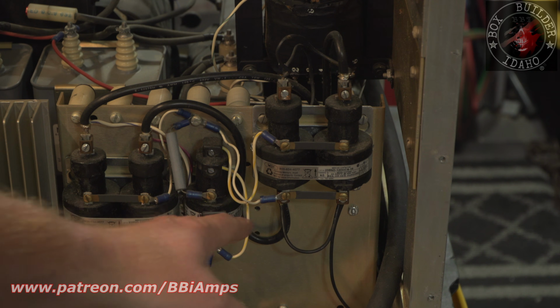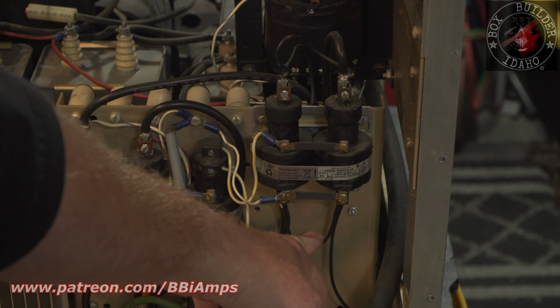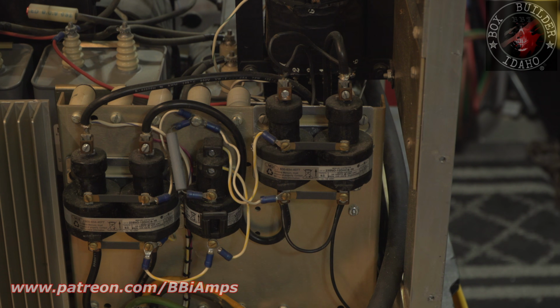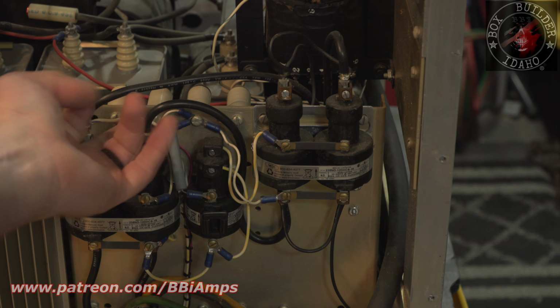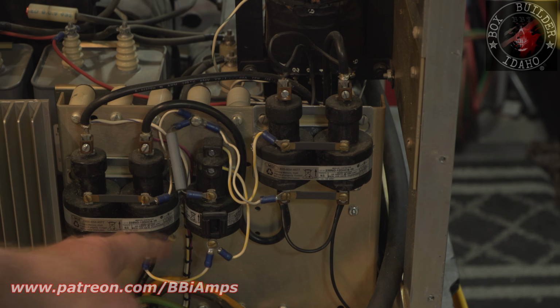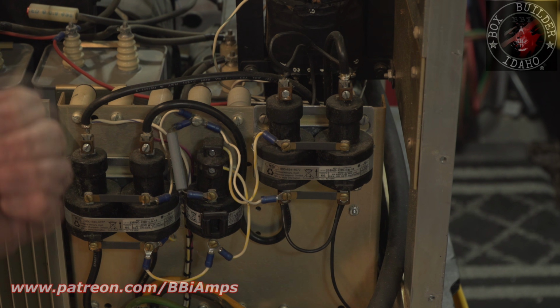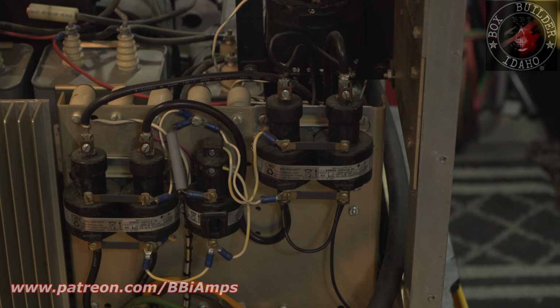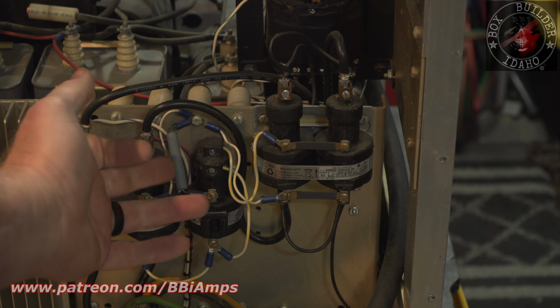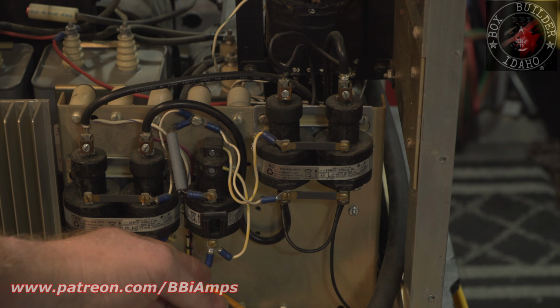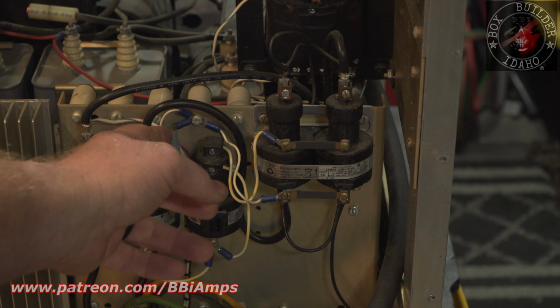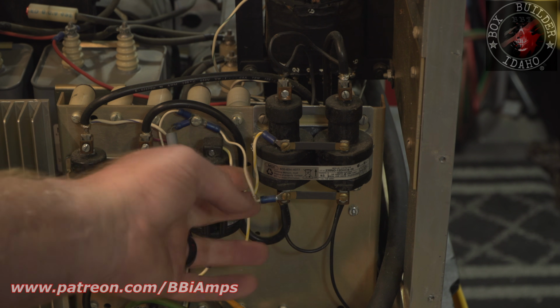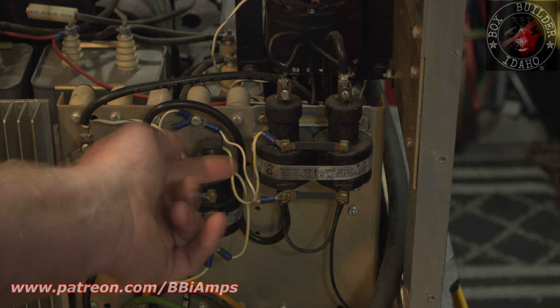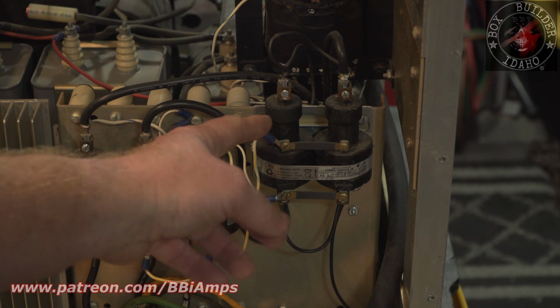For that to work, these have to be equal in size. This wire and this wire. You can see where these close, this closes, and this trips to this wire, which sends the 220 volts up to the head unit, the control interface. And the control interface sends a signal back down. This here, I think that doesn't run the coil, does it? Yes, it does. This runs the coil, and then this opens, and then this closes here, and then this fires this coil, and this goes to ground. And that's what causes this contactor to close.